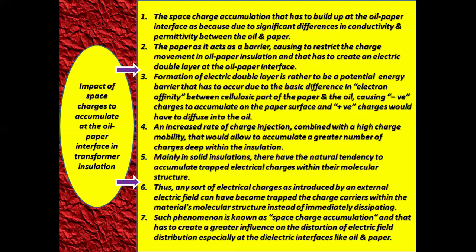Most important, any electrical charges introduced by an external electric field can become trapped charge carriers within the material's molecular structure instead of immediately dissipating. Such a phenomenon is known as space charge accumulation, and it has a great influence on the distortion of electric field distribution, especially at dielectric interfaces like oil and paper.